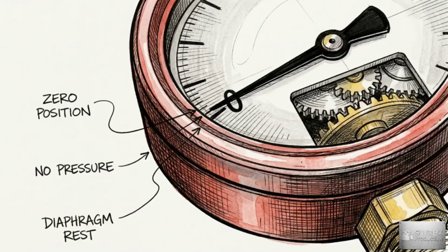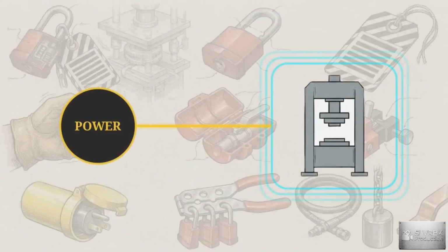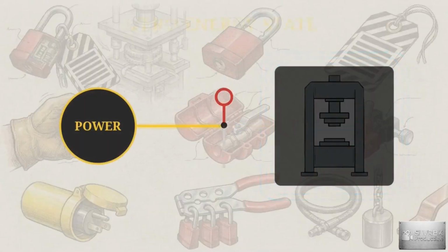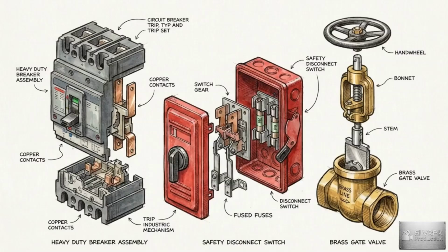The ultimate objective of the regulation is achieving a zero-energy state. This means the machinery is completely isolated from its power sources and rendered totally inoperative. Isolation requires the use of an energy-isolating device. These are physical hardware components like manually operated circuit breakers, disconnect switches, and heavy line valves.